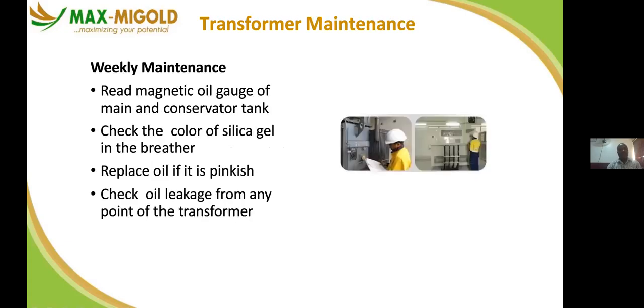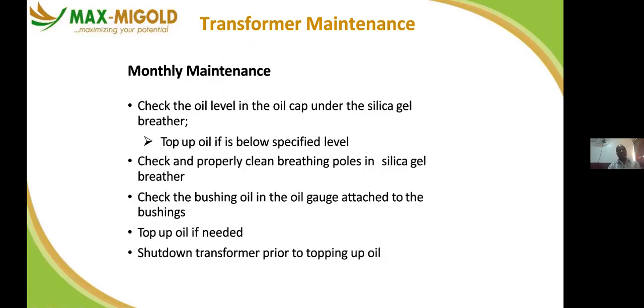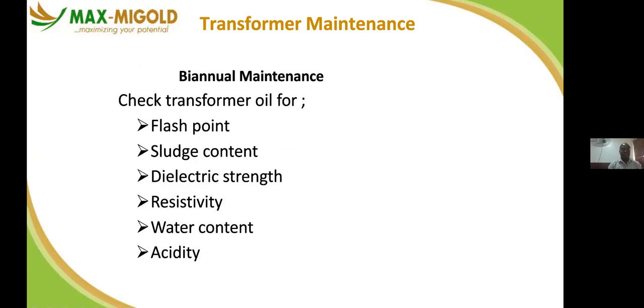So transformer maintenance. We have various types of maintenance on transformer. We have weekly maintenance. You check all this on weekly basis. We have one for monthly. This is where you check the oil level, the oil cap, the silica gel, and so on. You check them every month, if they have changed color or if the level of oil has dropped. We have the one for biannual maintenance, that's 6 months interval. The flash point, the sludge content. Some you take to the lab and test. There is a range that it must attain to know whether it's still okay or not. So these are resistivity tests, water content, acidity, and so on.